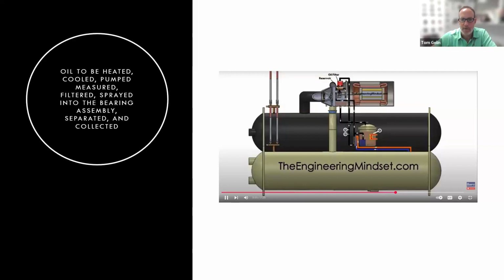I don't know if anybody will see my mouse or not, but behind the evaporator we've got an oil tank, sump, and we need this to be able to run at any time for startup. So there's a little heater to make sure the oil is viscous enough to get pumped, and in the lower left-hand corner of that tank is a little oil pump.